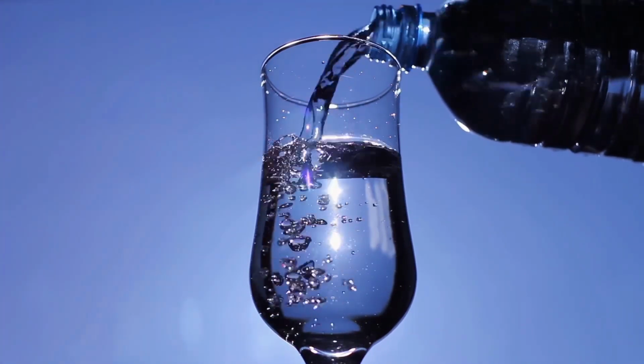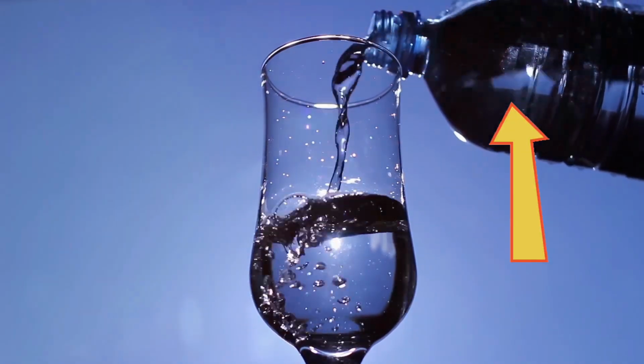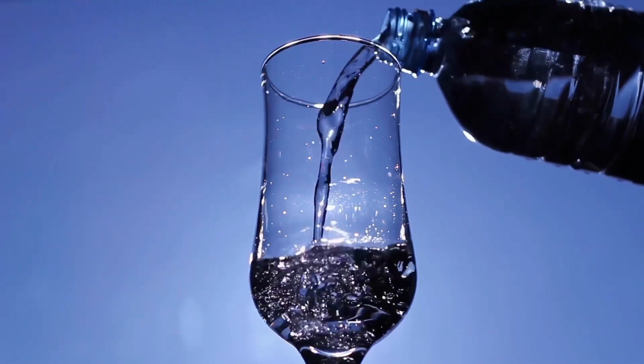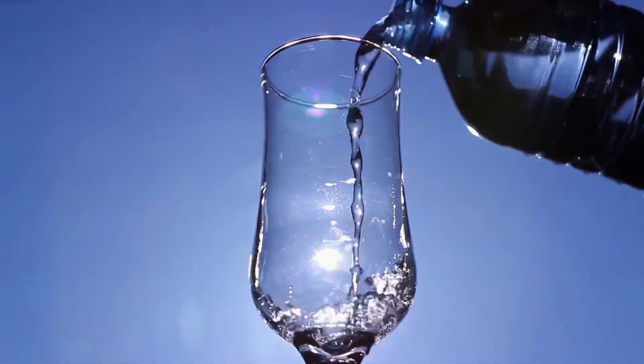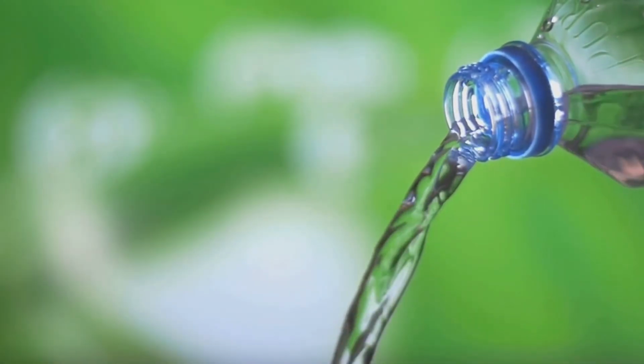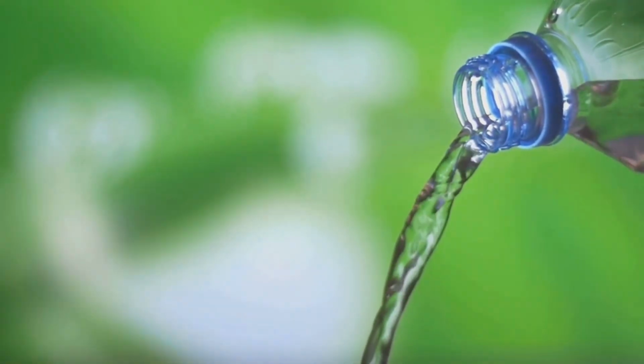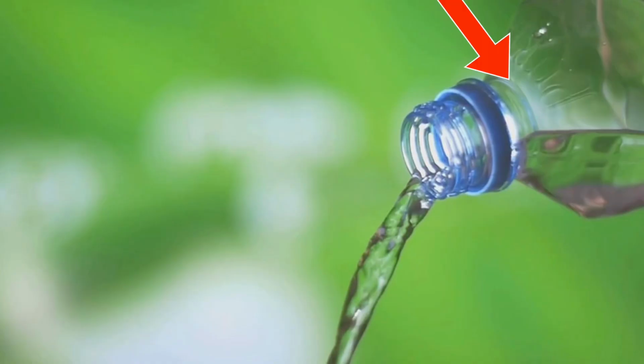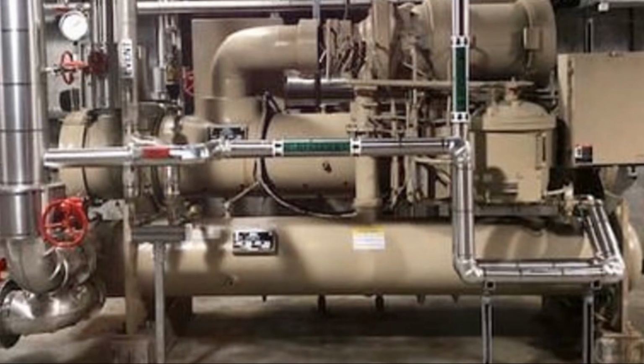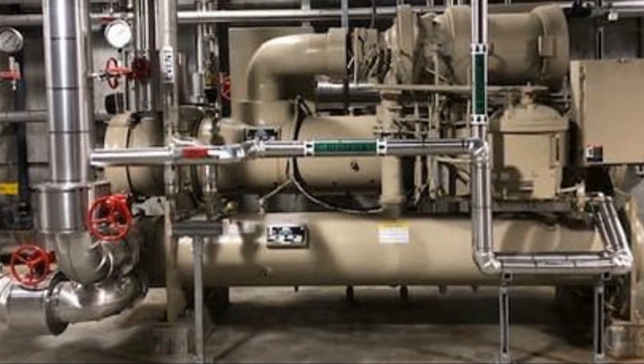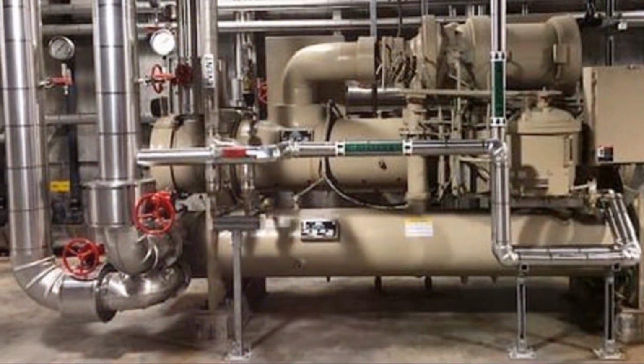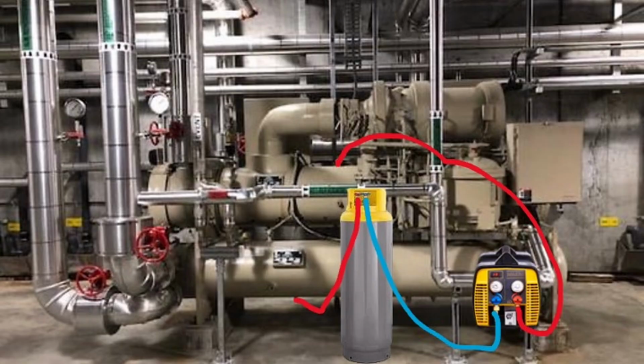The water will gurgle and slowly drain as the pressure on the top side of the water and the outlet of the bottle try to equalize. Now poke a hole in the bottom of the water bottle and all of the water rushes out of the bottle rapidly because the pressure is equalizing at the same rate that the water is leaving the bottle. This is the same physics behind using the push-pull method of refrigerant recovery. Okay, back to it.